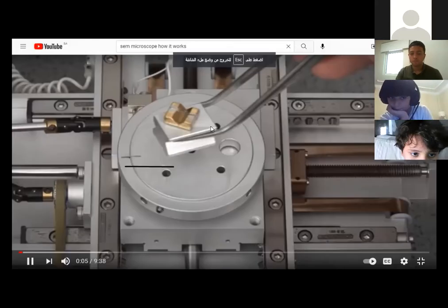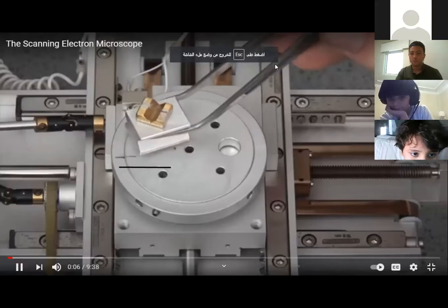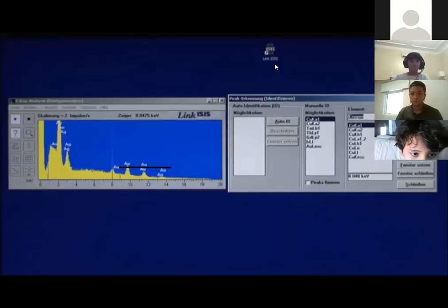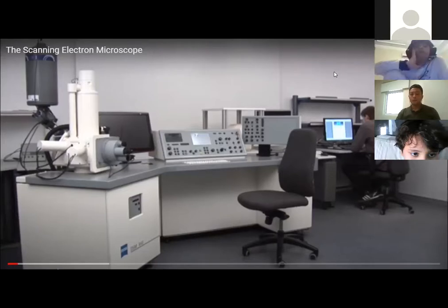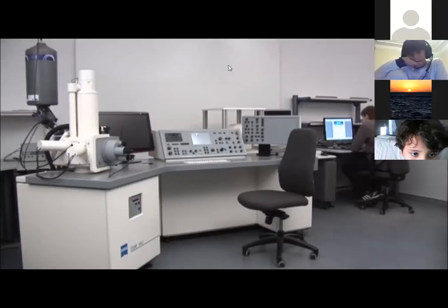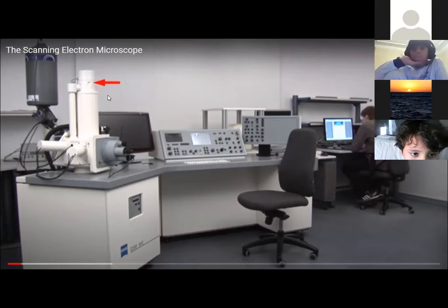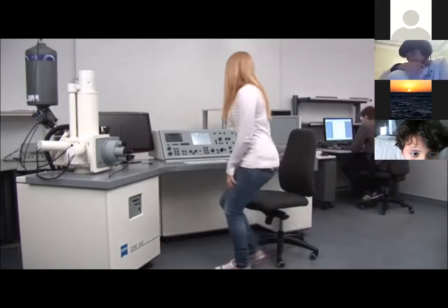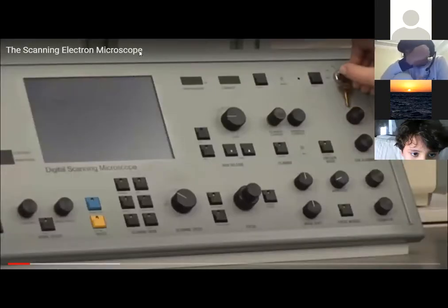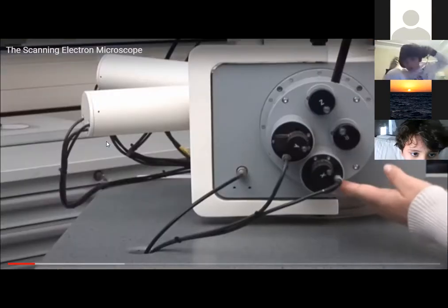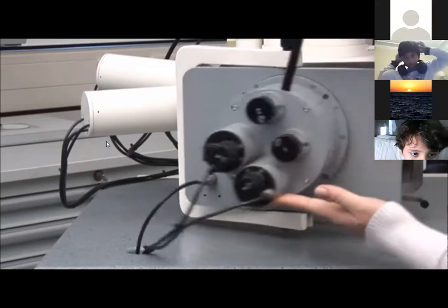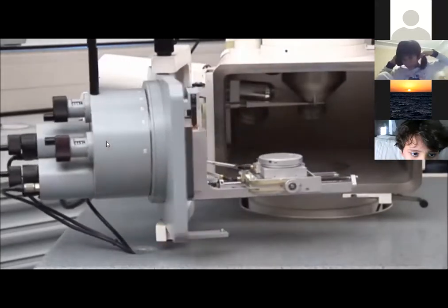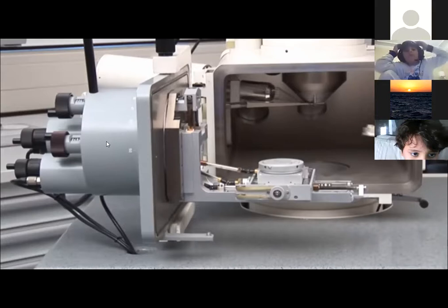Scanning electron microscopy is one of the most fascinating examination methods. This video shows how it works in practice. Main components of the microscope are column for electron beam generation, specimen chamber, vacuum pump, monitor, and control panels. The material tester turns on the vacuum pump control and vents the specimen chamber. After pressure equalization, she can open the cover plate of the specimen chamber. Together with the cover plate, the stage pans forward. Now different specimens can easily be placed on the round stage.